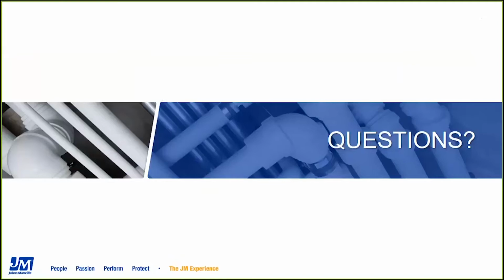Great, thanks, Sean. The next one is for you, Lance, and that is, can you double layer jacketed material to improve R values? Well, you can certainly double layer material to improve R values. Typically, we wouldn't recommend the inner layer of insulation having a jacket. You do want to make sure that the temperatures that are interacting with the jacketing are below that 140-degree range. So embedded within a double layer system, that jacketing would not be recommended. And then same on a chilled system. Again, the jacketing could be a concern, as you don't want to create an inner vapor barrier and an outer vapor barrier. So certainly you can increase R value with double layered systems, but it's not recommended to have jacketing on the inner layer. Great, thank you, Lance.